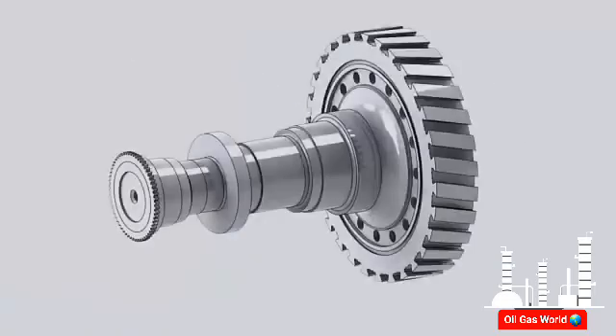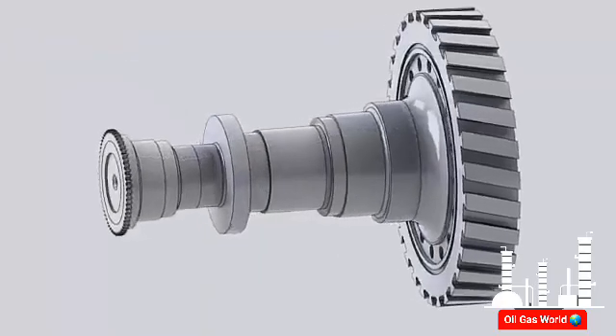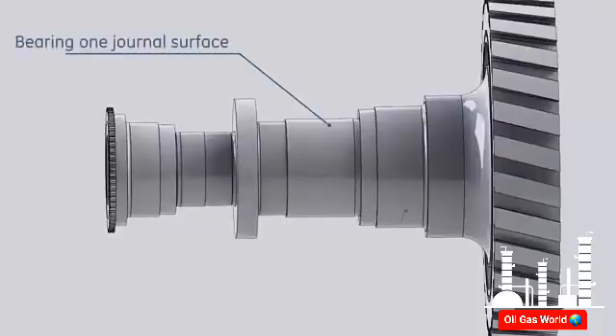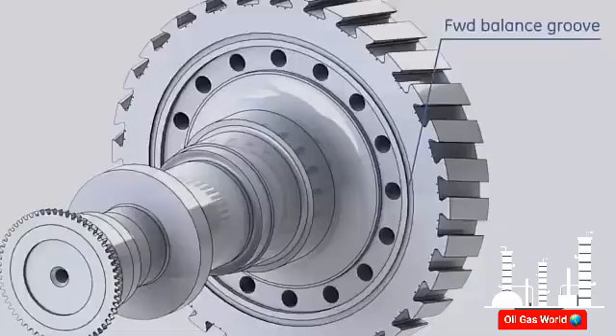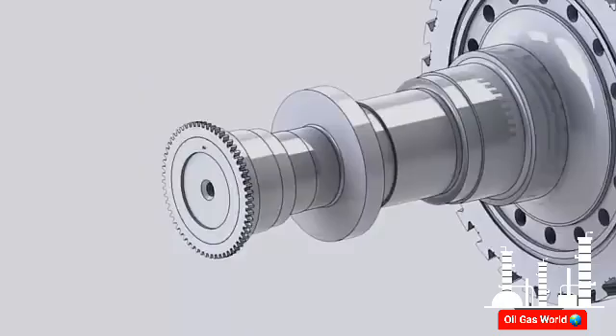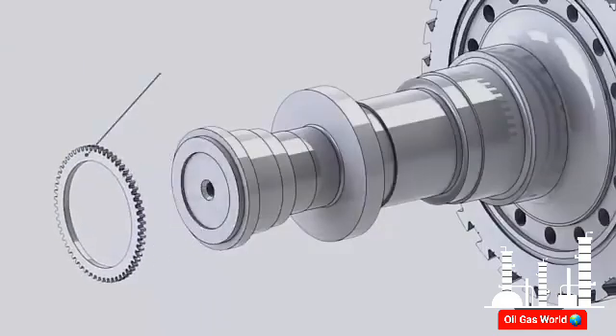The forward stub shaft is machined to provide the following features: a thrust collar, which carries the axial downstream and upstream thrust forces to prevent rotor axial movements; a journal surface for bearing number one and surfaces for oil and air seals; a forward balancing groove to add balancing weights for vibration control; and a forward flange to connect the gas turbine shaft to the auxiliary gearbox. A speed ring with 60 teeth is attached to the forward flange for speed measurements and protection.